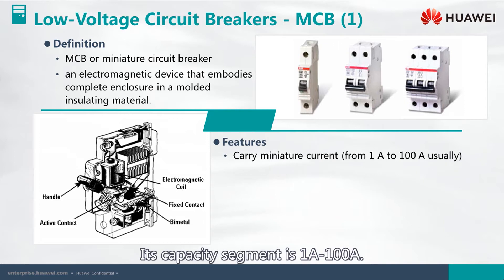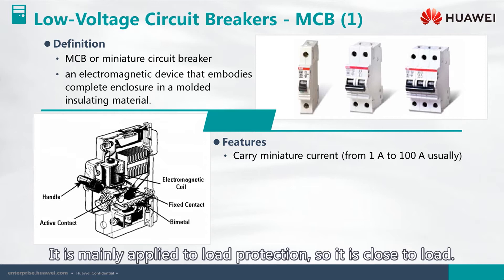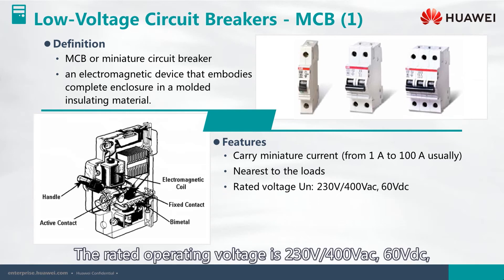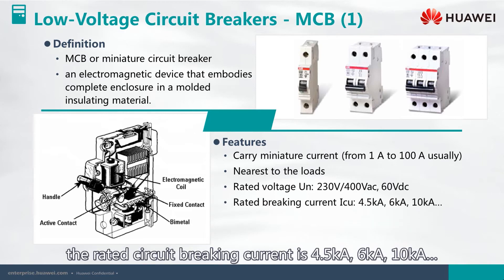Its capacity range is from 1 to 100 Ampere. It is mainly applied to load protection, so it is placed close to the load. The rated operating voltage is 230 V or 400 V for AC, and 60 V for DC. The rated circuit breaking current is 4.5 kA, 6 kA, or 10 kA.